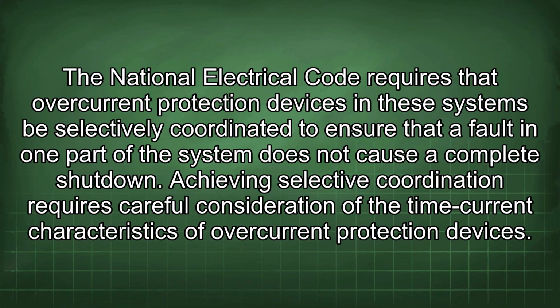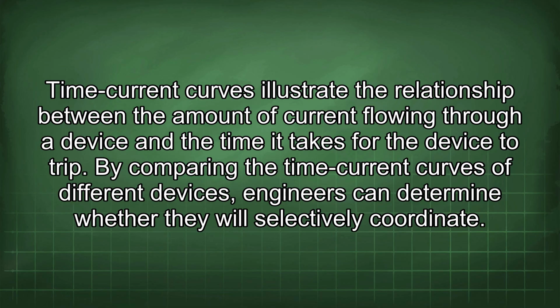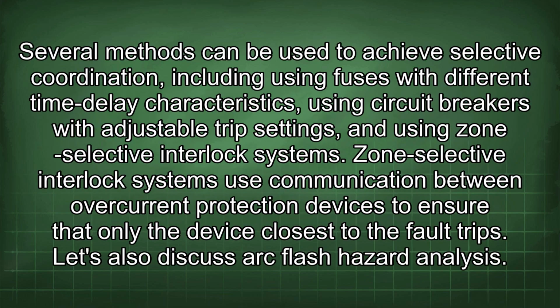Achieving selective coordination requires careful consideration of the time current characteristics of overcurrent protection devices. Time current curves illustrate the relationship between the amount of current flowing through a device and the time it takes for the device to trip. By comparing the time current curves of different devices, engineers can determine whether they will selectively coordinate. Several methods can be used to achieve selective coordination, including using fuses with different time delay characteristics, using circuit breakers with adjustable trip settings, and using zone-selective interlock systems. Zone-selective interlock systems use communication between overcurrent protection devices to ensure that only the device closest to the fault trips.